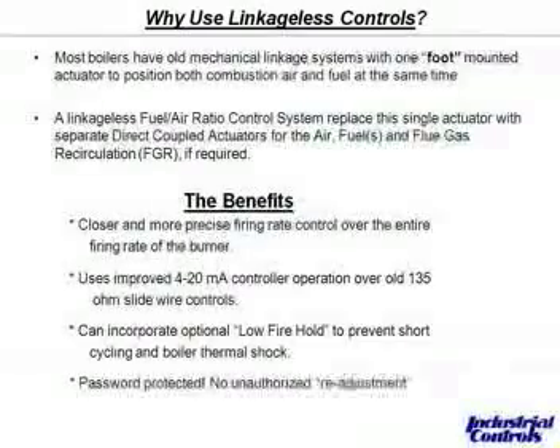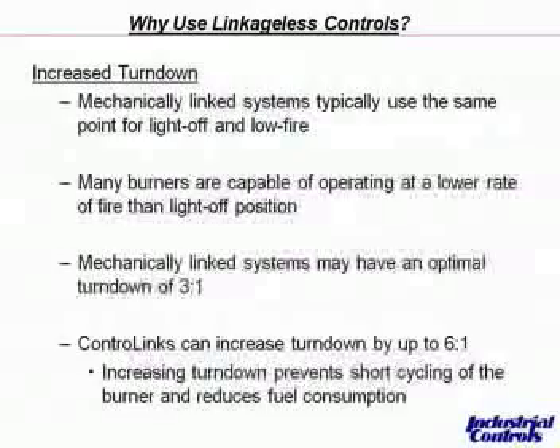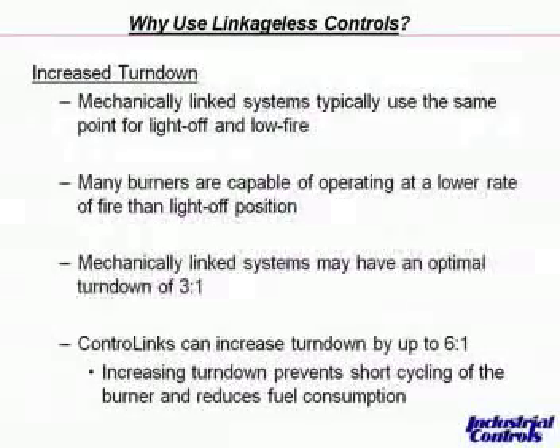The benefits include closer and more precise firing rate control over the entire firing range of the burner. Users get improved 4-20 milliamp control operation over the old slide wire 135 ohm. It can incorporate low-fire hold to prevent short cycling and boiler thermal shock during startups, and it's password-protected so no unauthorized readjustment can take place once the curve has been set. Regarding increased turndown: mechanically linked systems typically use the same point for light-off and low-fire, but many burners are capable of operating at a lower rate of fire than light-off. You typically see mechanically linked systems with an optimal turndown of 3-to-1, and that can be increased up to 6-to-1 using ControLinks, which prevents short cycling and reduces fuel consumption. It's always important to check with the equipment manufacturer to make sure their burner is capable of operating at this lower turndown rate.